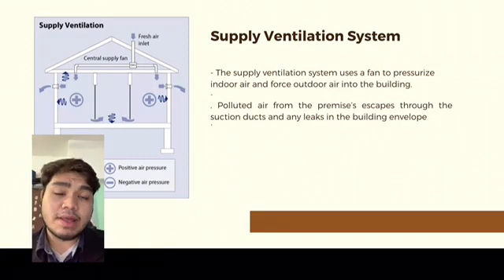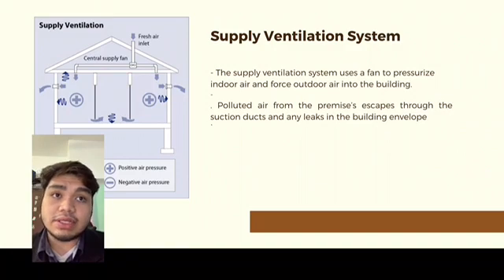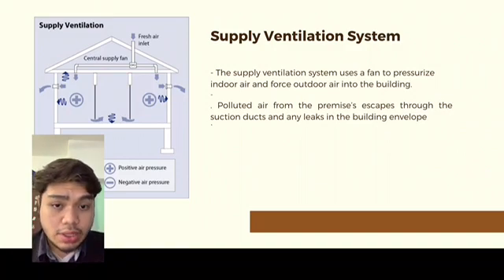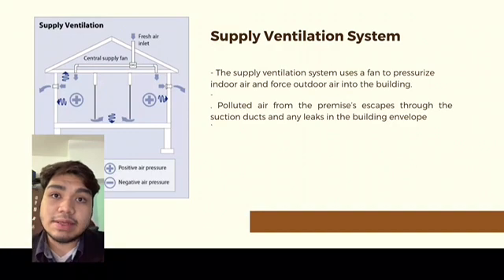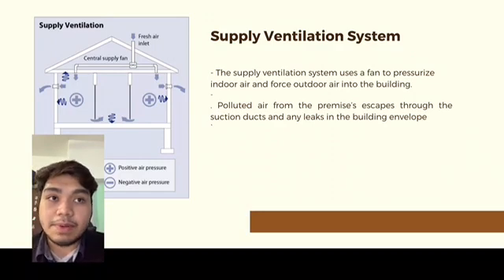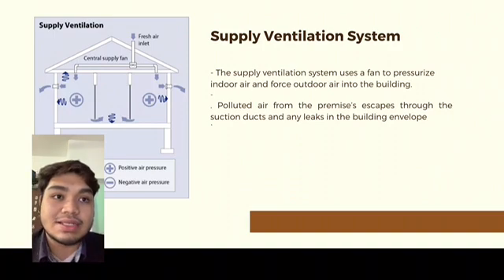The second one is the supply ventilation system. The supply ventilation system uses a fan to pressurize indoor air and force outdoor air into the building. Polluted air from the premises escapes through the suction ducts and any leaks in the building envelope. This type of mechanical ventilation allows better control of the air supply than extraction ventilation. By pressurizing the home, supply ventilation reduces the possibility of pollutants entering the room and inhibits the return of combustion gases produced by fireplaces and other appliances. They dehumidify and filter the air entering the house to eliminate dust.